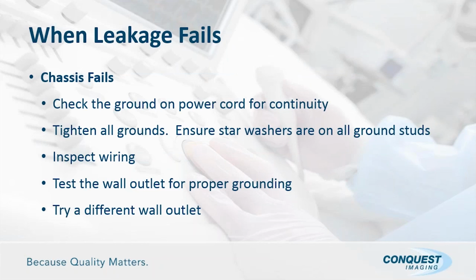So what about when you've done everything correctly, you've set it all up, you've checked all your conditions, but for whatever reason your leakage still fails? We need to talk about some of the things we can check when this condition happens. Again, let's say chassis leakage fails. Well, you want to check the ground on the power cord for continuity, and we already did that earlier in the presentation, when we talked about how to check your power cord for continuity.